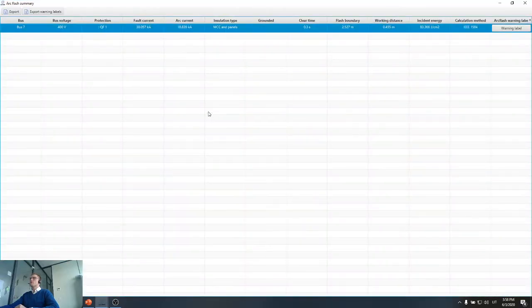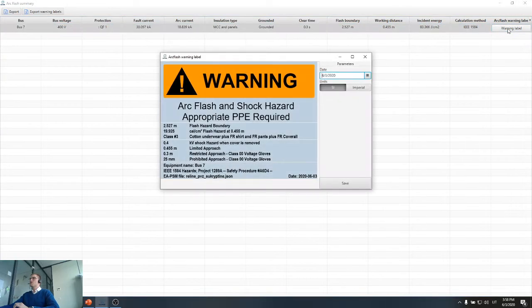Okay, so calculations are done. We can see first of all that the flash boundary was reduced by almost half a meter. Fault current was also reduced. Instead of 42 kiloamps, something like that, now it's only 30 kiloamps, so much smaller. And incident energy was also reduced. And okay, so we have reached our goal. Actually, this kind of reactor would be enough to reduce the flash boundary, so that in order to work with this kind of network, class 3 personal protection equipment should be enough.